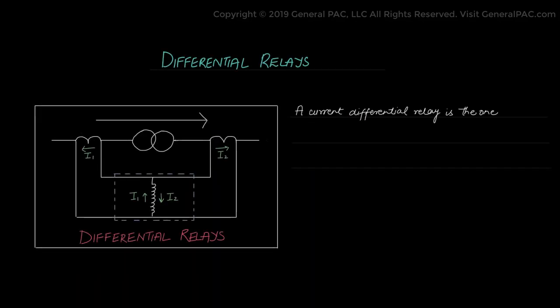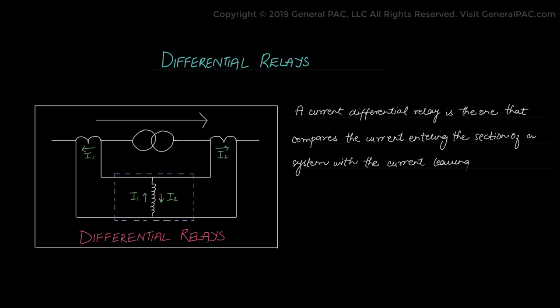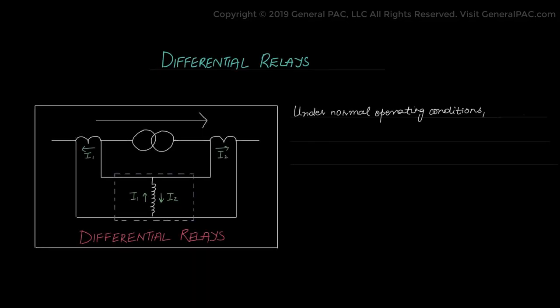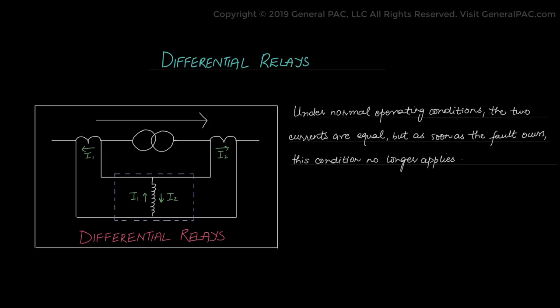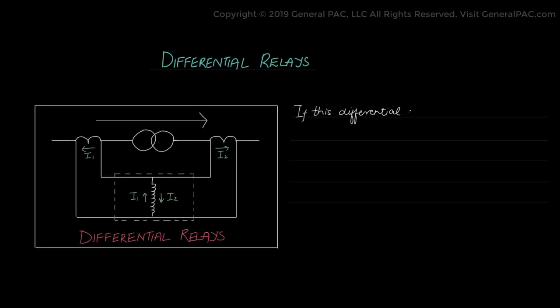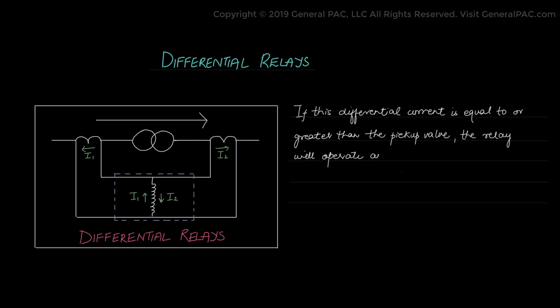The mechanism for a differential relay works as follows. A current differential relay compares the current entering a section of the system with the current leaving the section. Under normal operating conditions, the two currents are equal, but as soon as a fault occurs, this condition no longer applies. The difference between the incoming and outgoing current flows through the operating coil of the relay. If this differential current is equal to or greater than the pickup value or set point, the relay will operate and open the circuit breaker to isolate the faulty section.